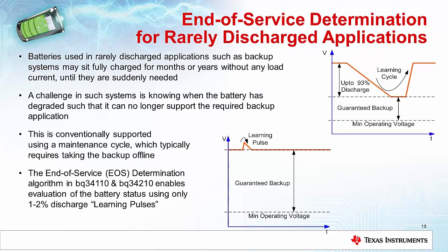Another algorithm that I'm going to talk about is our end of service determination. This is focused specifically on rarely discharged applications. These are like backup systems where you have batteries that may sit fully charged for months or years without actually having any discharge until suddenly they're used when there's an emergency. The challenge here is, how do you know that the battery is still good, that it still has enough health and capacity to supply the backup that's required by the system? Or should it have been replaced at some point earlier, before this backup occurred?